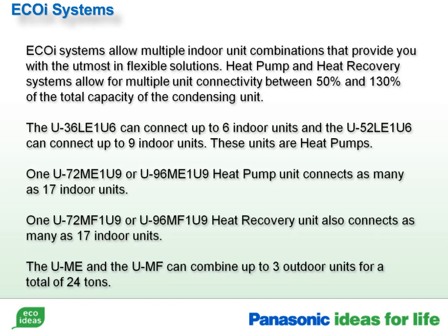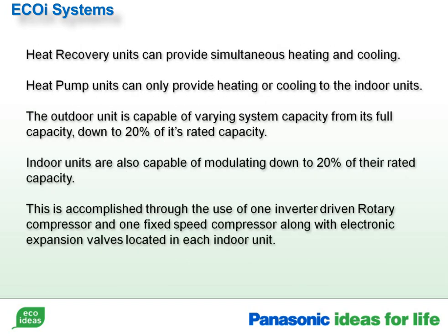1 U72 ME1U9, or 1 U96 ME1U9 heat pump unit, connects as many as 17 indoor units. 1 U72 MF1U9, or 1 U96 MF1U9 heat recovery unit, also connects as many as 17 indoor units. The U-ME and the U-MF can combine up to 3 outdoor units for a total of 24 tons. Heat recovery units can provide simultaneous heating and cooling. Heat pump units can only provide heating or cooling to the indoor units.